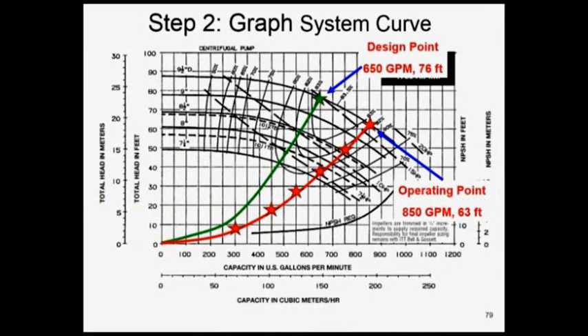We don't need 850. And we don't need to throttle back on it to get to 650, do we? We need to trim the pump impeller. We need to trim this pump impeller. What size do we go to? How do we get to the size? Right now we're at 9.5 inches. And if we don't throttle back, we're going to throw 850, which we don't need. So what do we need to do? All right, just don't throttle anything. You tell me what flow rate we need. I think it was 650, right?